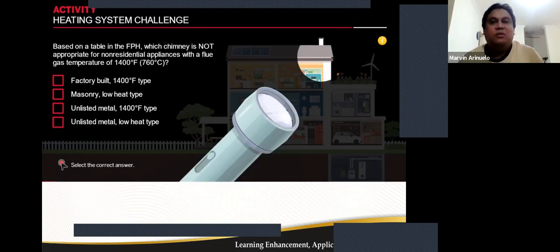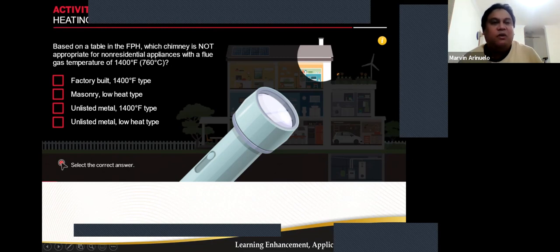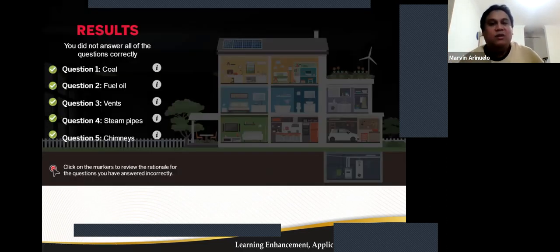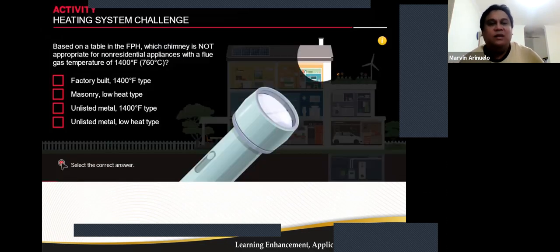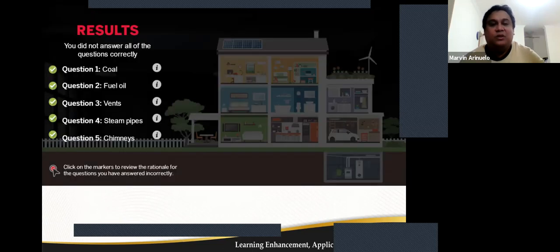Based on the table in the fire protection handbook, which chimney is not appropriate for a nonresidential appliance with a flue gas temperature of 1,400 degrees Fahrenheit? Again, you will use table 10.2.14, which indicates that the unlisted metal, low heat type chimney is not appropriate for a non-residential appliance with flue gas temperature of about 700 degrees centigrade. So the answer here is D. You see, we answered all of those and provided our answers. The answer here is D according to your fire protection handbook.